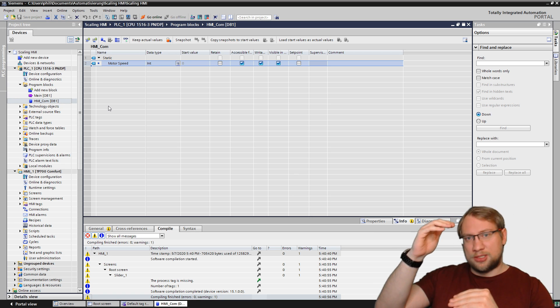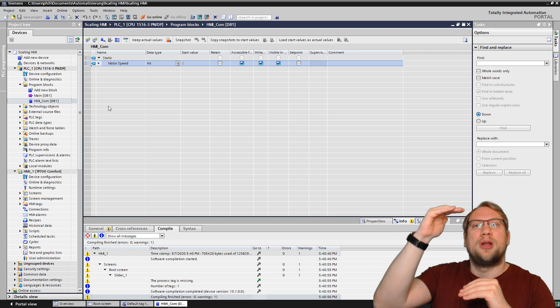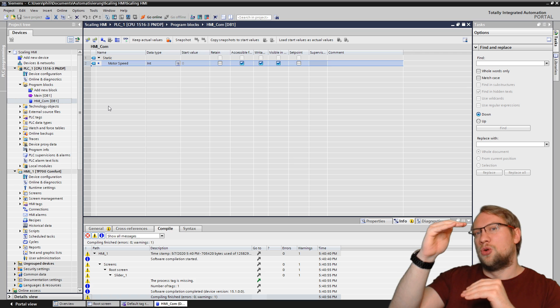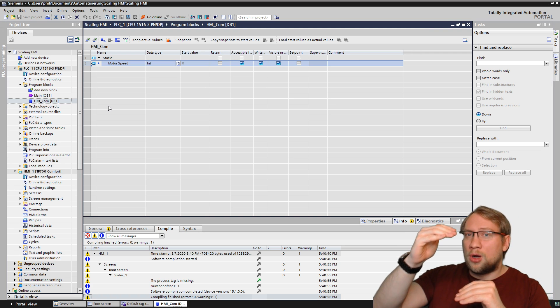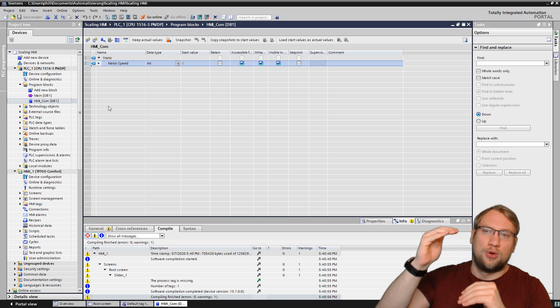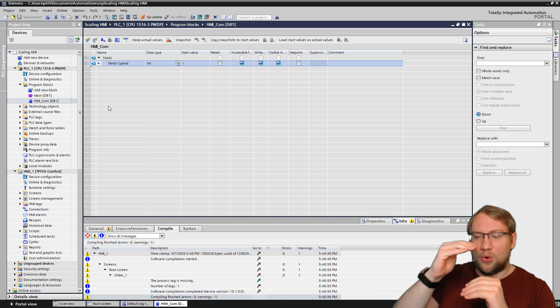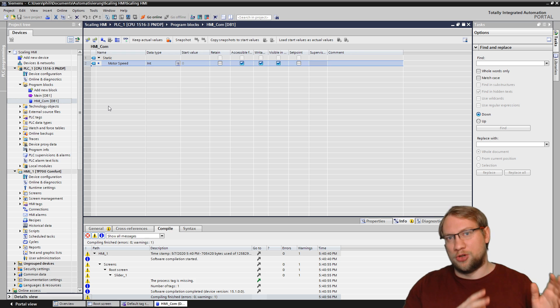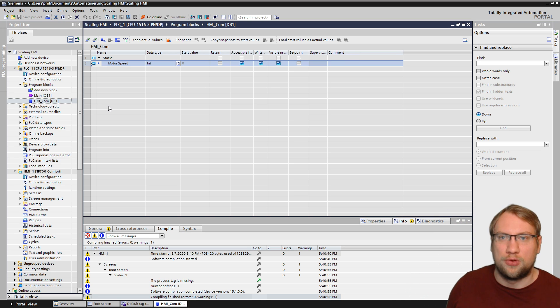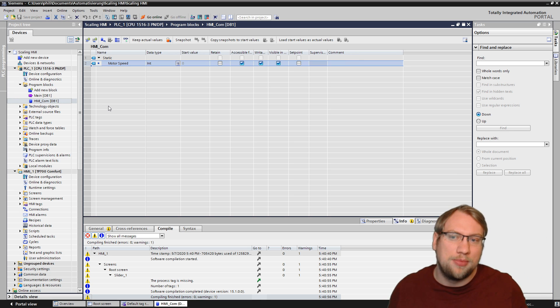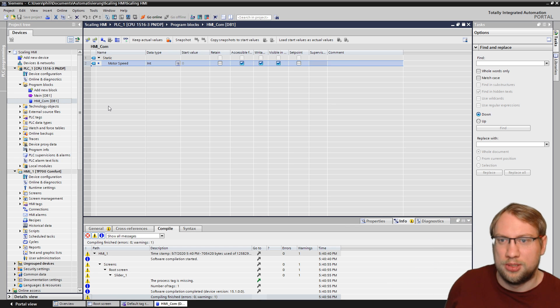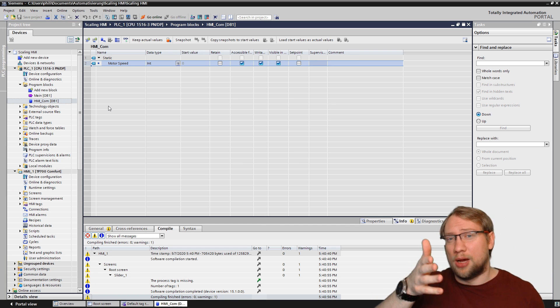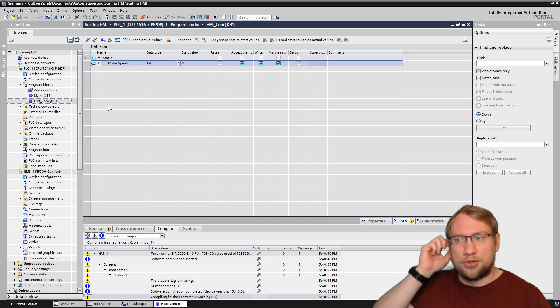Like 0 is 0 speed as motor off and 32,767 is 100% of the motor speed. So what would you rather put in 32,000 or 100% or 16,200 something or 50%? Of course, you would like to go with the percent or with the RPM respectively, which is of course then in the end the same that you in the scaling procedure you can use it for both the RPM and also the percentage. I will just show you the percentage. RPM is pretty easy than on your own.